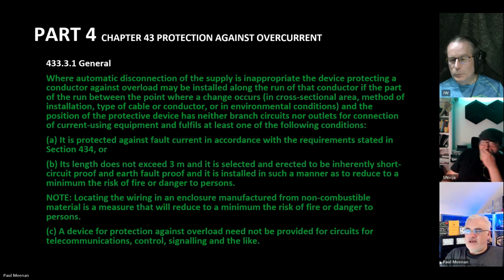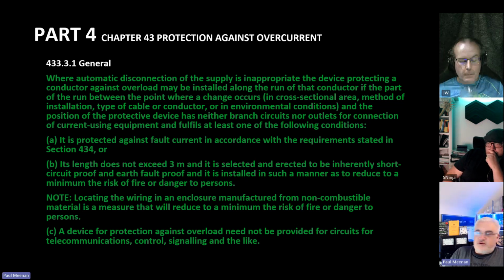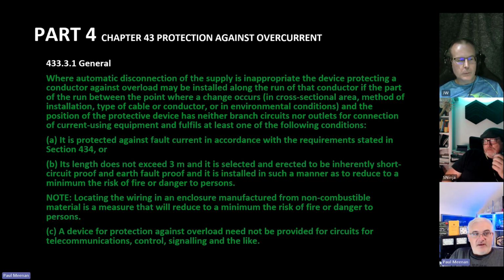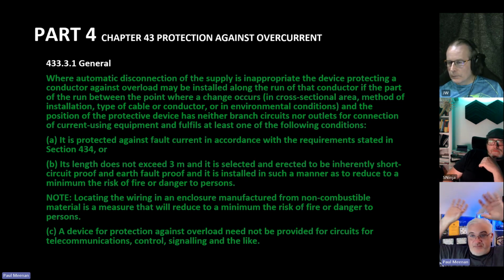Yeah. I think the opening statement's weird, because the original one was a device for protection against overload need not be provided, and now it's gone on this monologue. But I do actually agree with it to an extent. So on the underground, for instance, on the 110 volt sockets on the platform, we would design for volt drop, say 30, 50 mil cables that you'd have to run along the platform because the volt drop on 110 was ridiculous. Take it into a junction box, fixed base connectors, and then drop down to like a 10 mil or a 6 mil to get it into the back of the 110 socket.